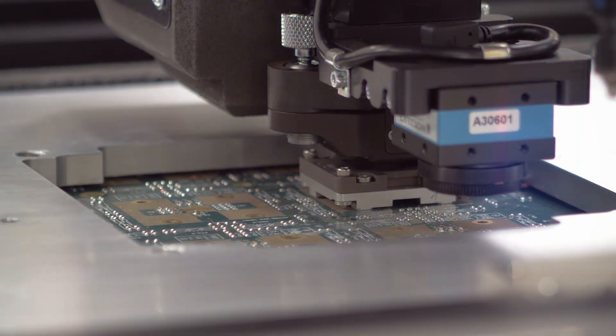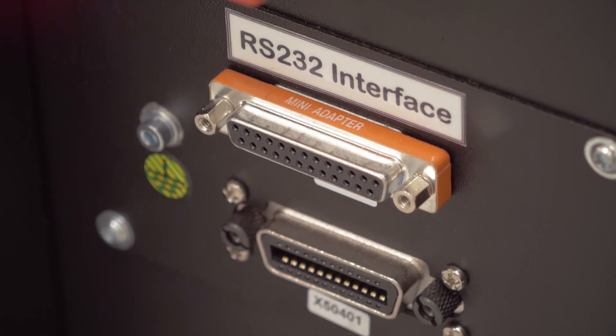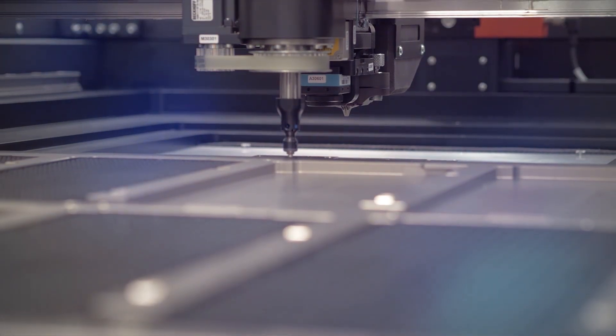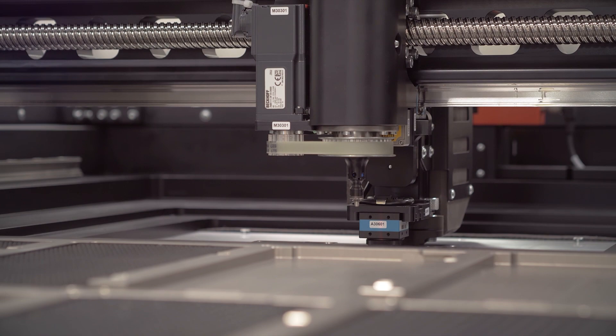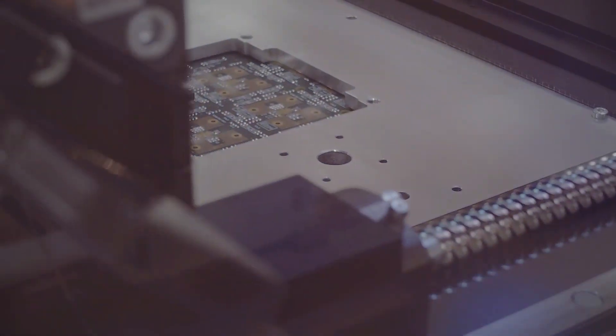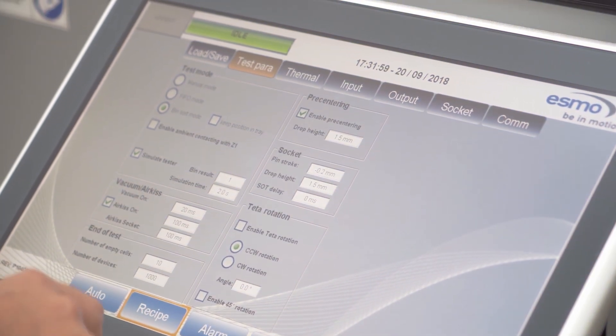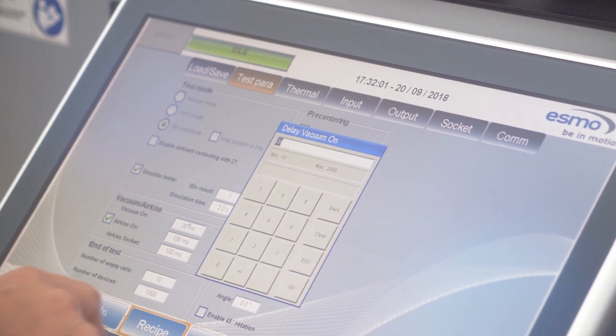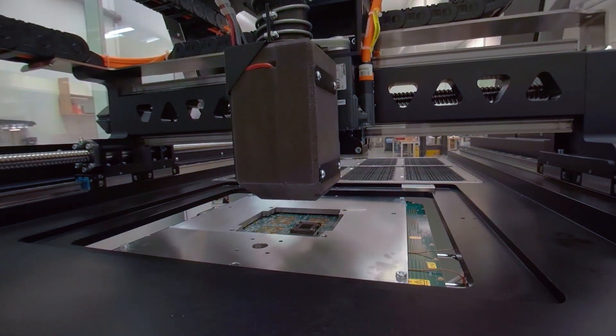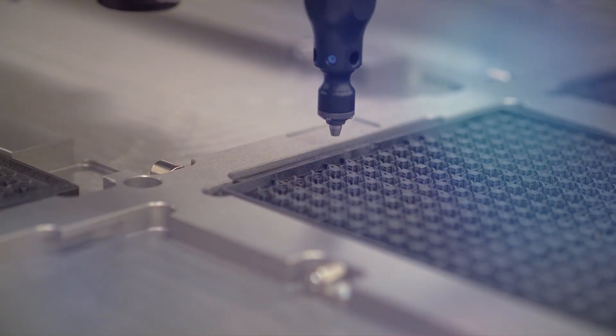The Talos temperature control system further allows for changing the set temperature from the tester via GPIB or RS-232 for fine adjustment in the course of testing, for single insertion at multiple subsequent test temperatures, as well as for multiple tests at different set temperatures without user interaction. The system interior is sealed and purged to prevent icing. The fully integrated, handler software-controlled cooling unit offers a choice of two configuration options: an electrical chiller or an LN2 heat exchanger. Based on its modular design, the Talos temperature system may be expanded as per individual requirements.